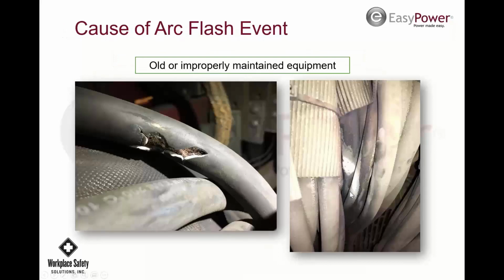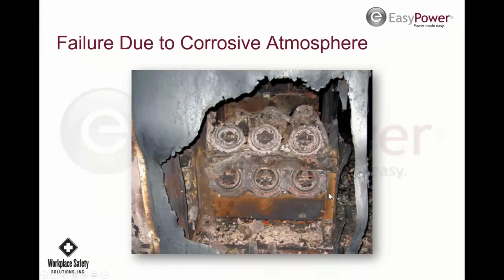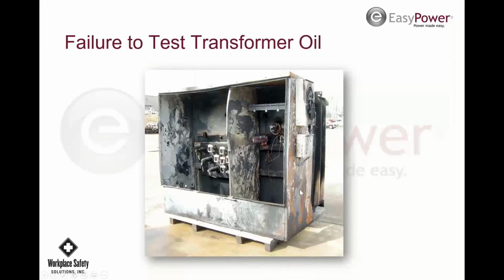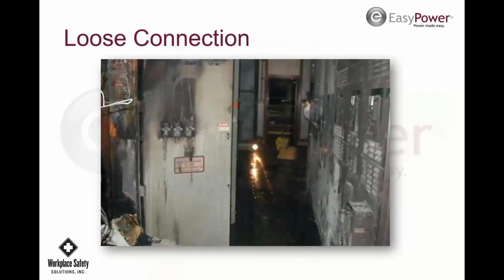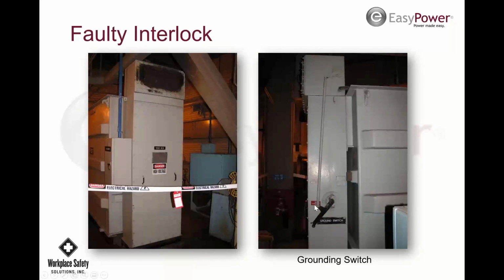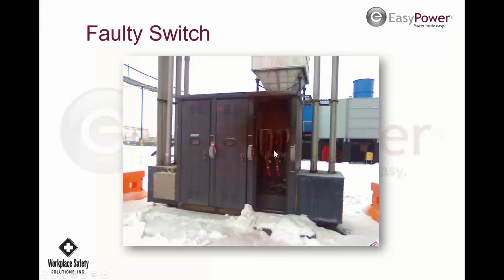The other places where arc flashes occur: bad cables. If you see stuff like this, these are generator cables, lock it out. Make sure it's shut down until it's fixed. Other things that can have an impact on arc flash are corrosive atmospheres and damage from dust and fumes. Also not properly testing transformers and having oil fail. Transformer oil needs to be tested to make sure the oxygen level is proper and there's no carbon buildup and so forth. Loose connections can cause arc flashes. Sometimes failed interlocks cause someone to close a grounding switch on an energized bus without thinking. Faulty switches that should have been locked out but weren't, so that happens sometimes.